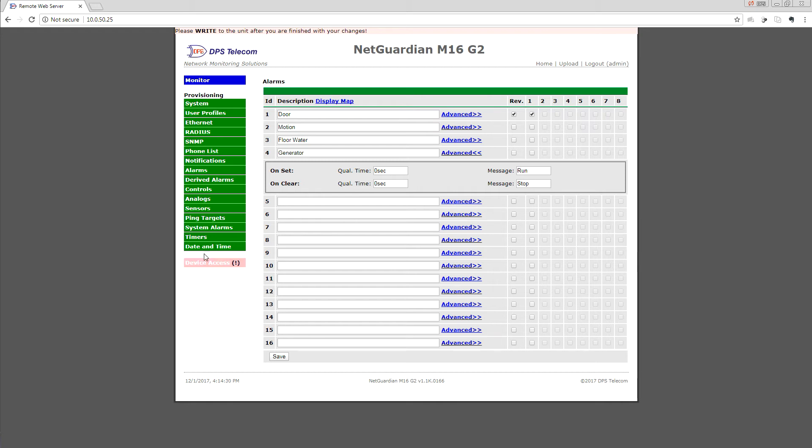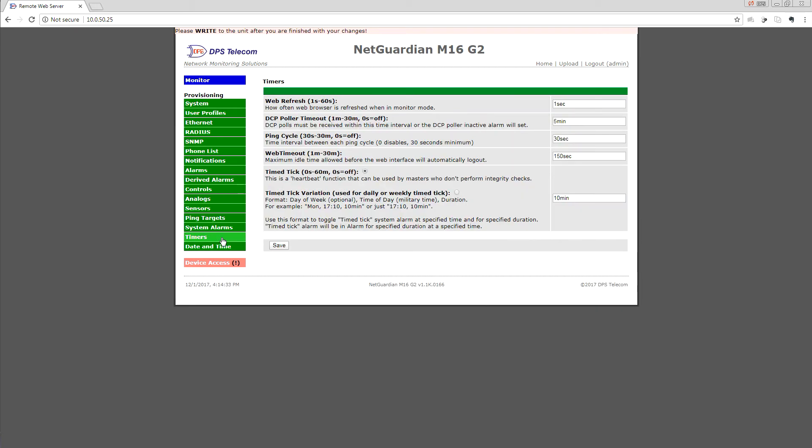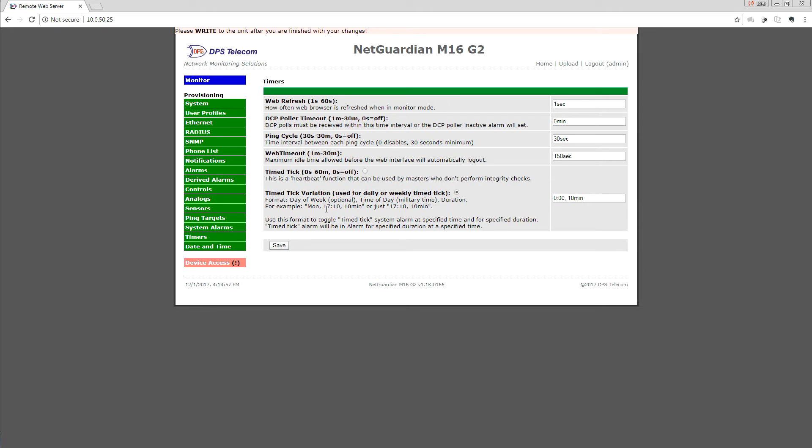We go to Timers to do that, and here we have a feature called Time Tick that historically was created so that the RTU could send an alarm every five minutes or every 30 minutes. This was just a keep-alive or heartbeat function to tell you, 'Yes, I'm still here.' But there's a time tick variation that we can use for scheduling, and that's what we want to select, so we'll click this radio button. You can see the format changed, and this lets us set this time tick point during a certain window on every day or only on a certain day of the week.